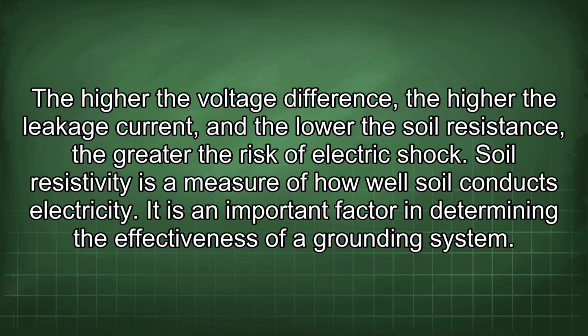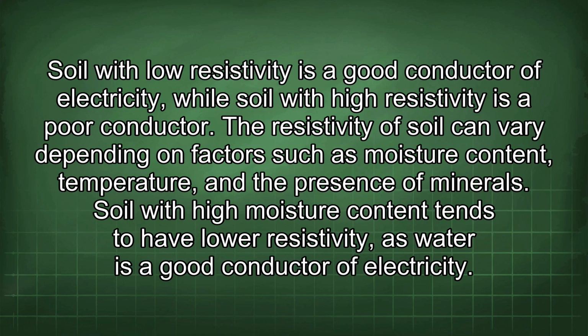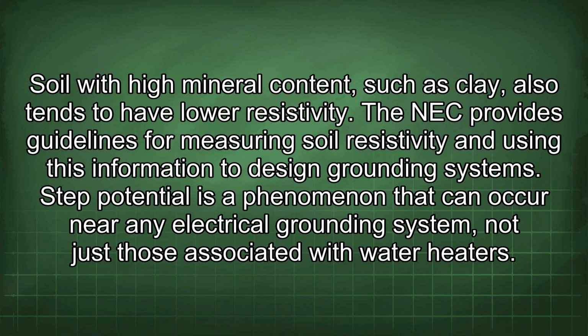Soil resistivity is a measure of how well soil conducts electricity. It is an important factor in determining the effectiveness of a grounding system. Soil with low resistivity is a good conductor of electricity, while soil with high resistivity is a poor conductor. The resistivity of soil can vary depending on factors such as moisture content, temperature, and the presence of minerals. Soil with high moisture content tends to have lower resistivity, as water is a good conductor of electricity. Soil with high mineral content, such as clay, also tends to have lower resistivity. The NEC provides guidelines for measuring soil resistivity and using this information to design grounding systems.